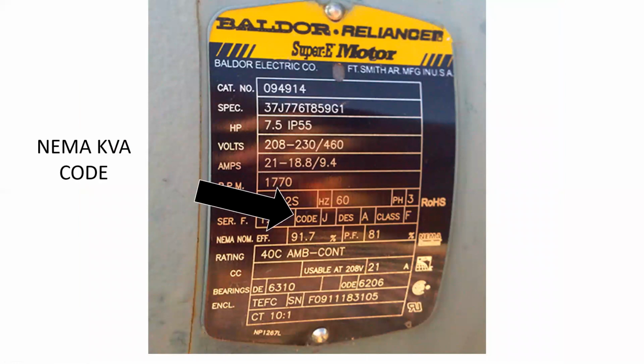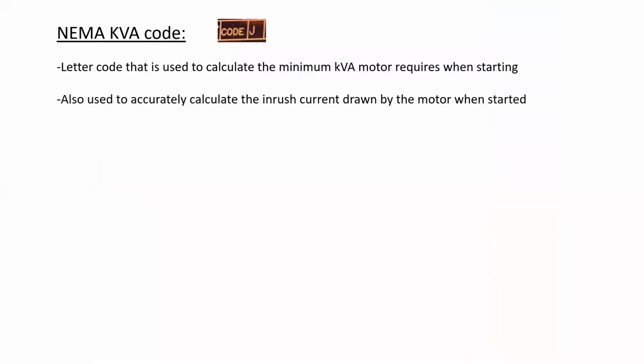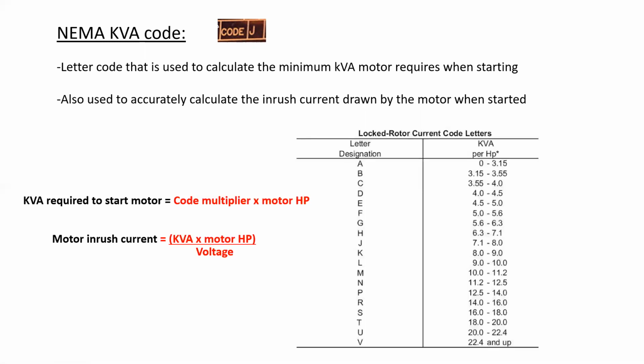NEMA KVA code. The KVA code for this motor is J. The letter code is used to calculate the minimum KVA the motor requires when starting. It's also used to accurately calculate the inrush current drawn by the motor when first started. The way that we utilize this information is we take the letter code to a NEMA table.